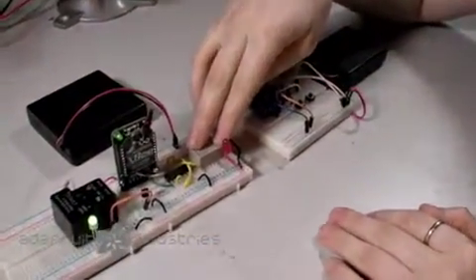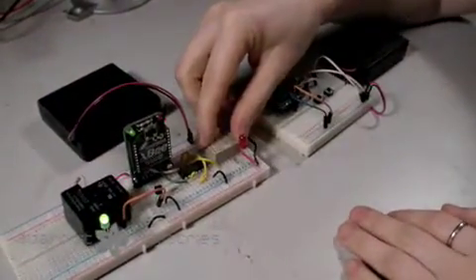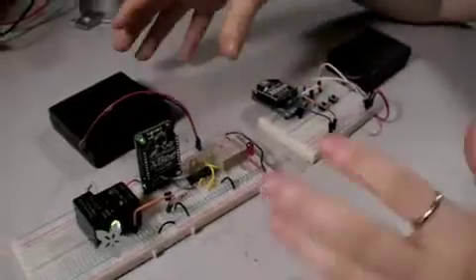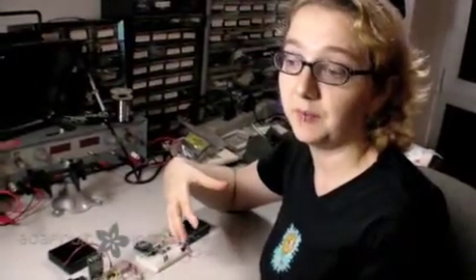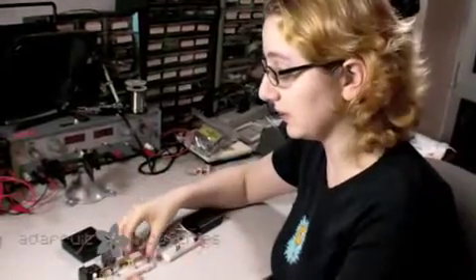This only needs a pulse. And also if the power goes out or they lose communication, you don't have a risk of the relay resetting. It only resets when it gets a signal.